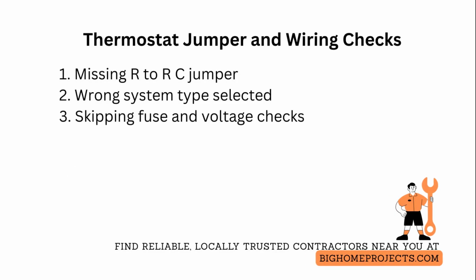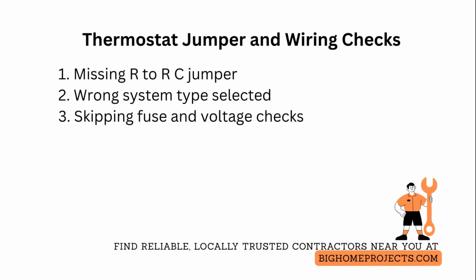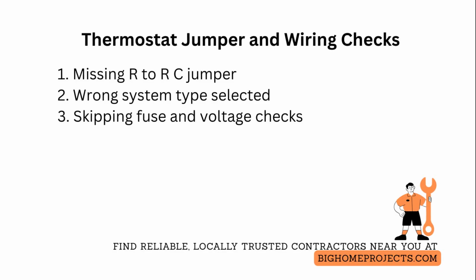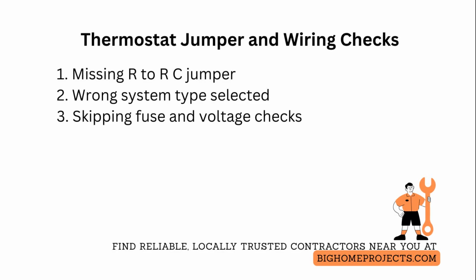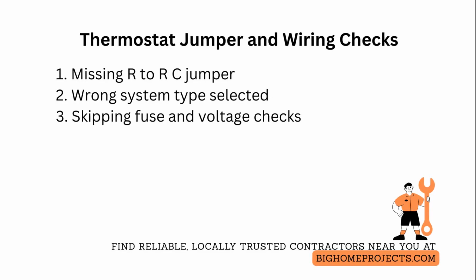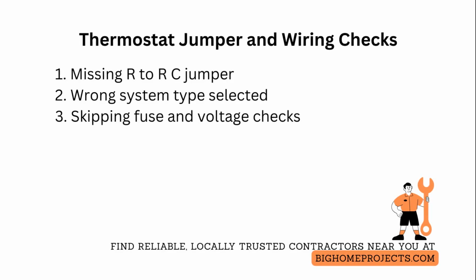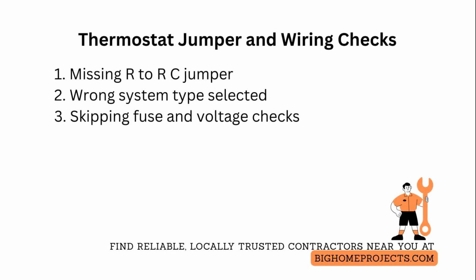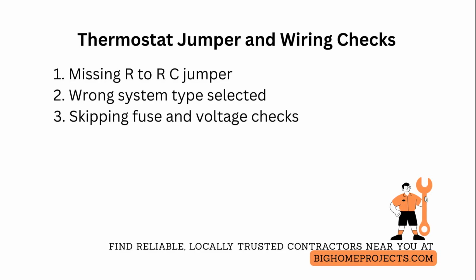One of the most common wiring mistakes is a missing jumper between R and RC, which causes thermostat cooling or heating not to operate. Fix it by confirming single transformer operation and adding the correct jumper or copying the OEM wiring diagram. One of the next frequent errors is misidentifying system type and selecting heat pump mode when you have conventional heating and cooling, which results in incorrect relay activation. Fix by checking the outdoor unit type and following the thermostat setup menus to select conventional forced air.